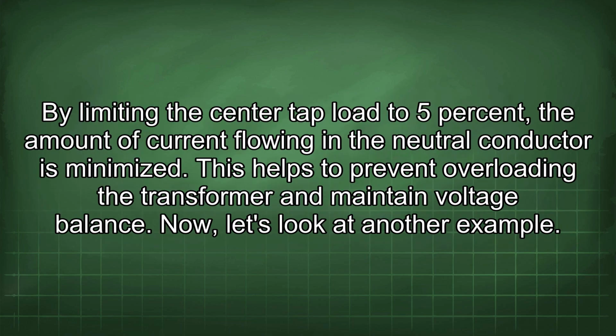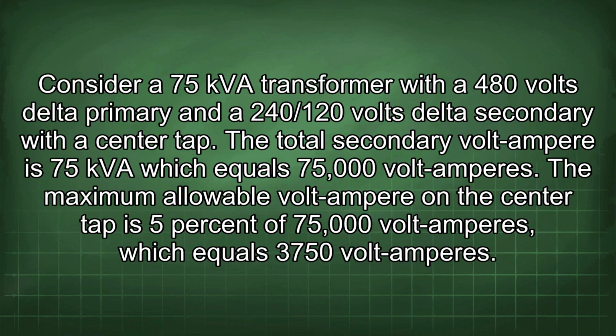By limiting the center tap load to 5%, the amount of current flowing in the neutral conductor is minimized. This helps to prevent overloading the transformer and maintain voltage balance. Now let's look at another example. Consider a 75 kVA transformer with a 480 volts delta primary and a 240/120 volts delta secondary with a center tap.